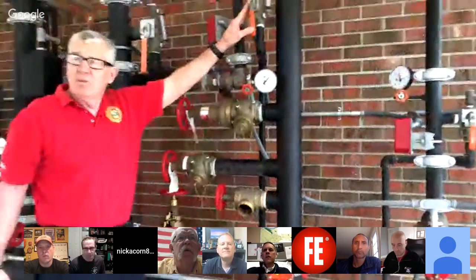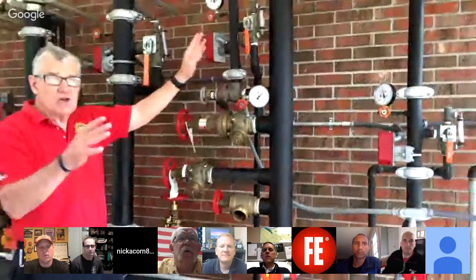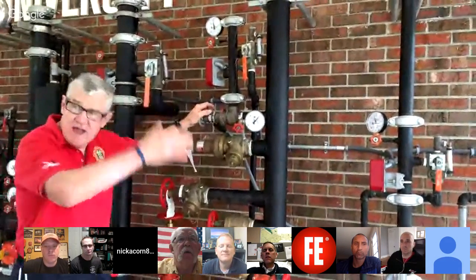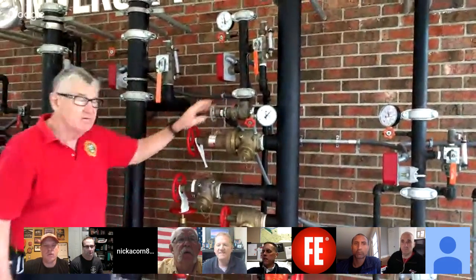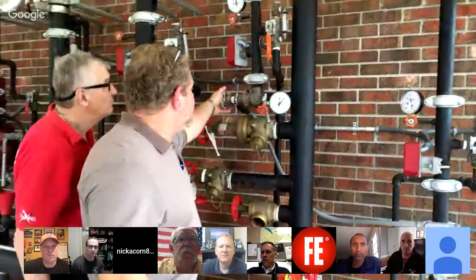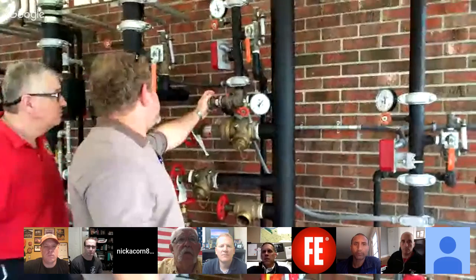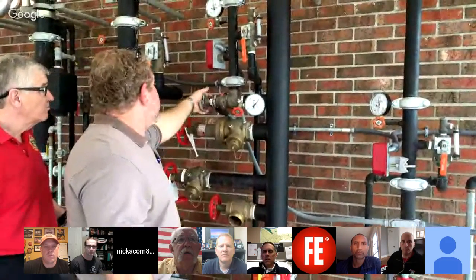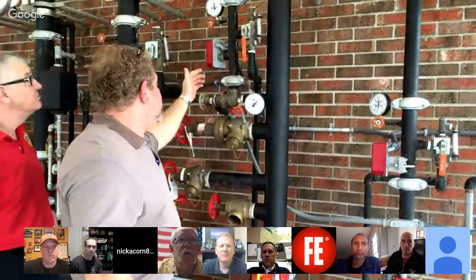Could you talk a little bit about the best way to shut off a sprinkler when it's a combination standpipe and sprinkler system? Yeah, absolutely. Go to the floor of origin, and then essentially you're going to close the control valve. And I can do it if you'd like. But we close the control valve. It'll actually send the system into supervisory.